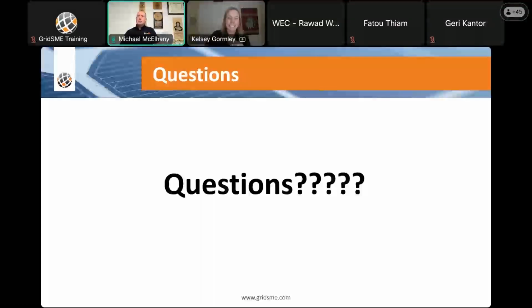I was going to say, Kelsey, a year ago at RE Plus in Anaheim, I introduced Kelsey to several of my inverter manufacturers, and that was one of the questions, because there really isn't a place where it gets tested. We've asked them, is there a way that you can lab test this, commission test this, and provide it? And the answer was no. So what we're left with is when a client gets a deficiency because there was an event and they weren't able to produce the information, especially specific to the 1 millisecond time sync and the 10 millisecond data sampling. We've been working with them. We're not getting much headway, but there is no explicit requirement to test it today.